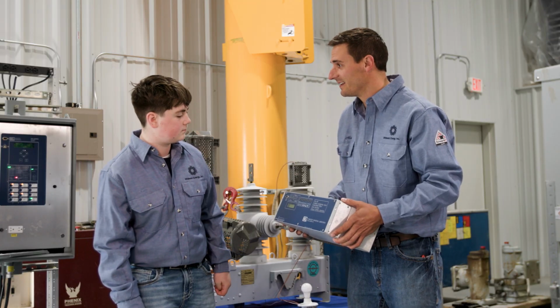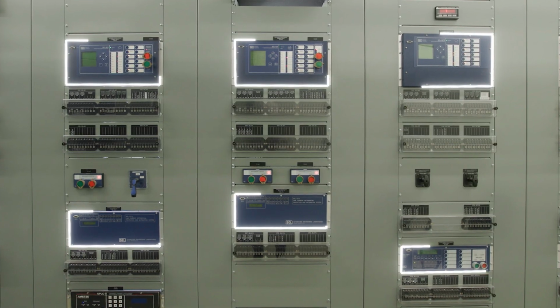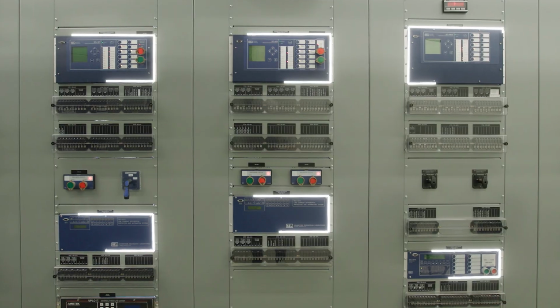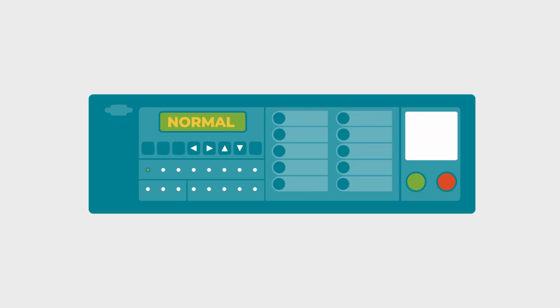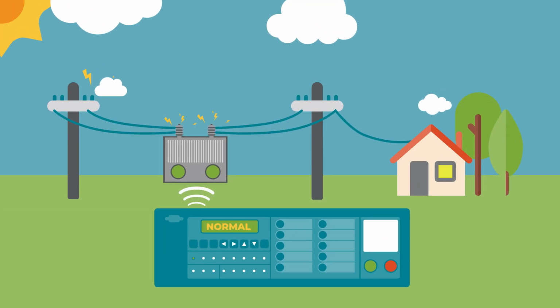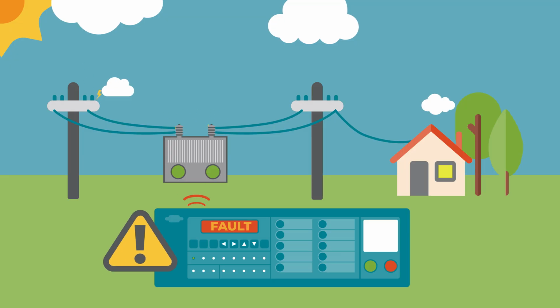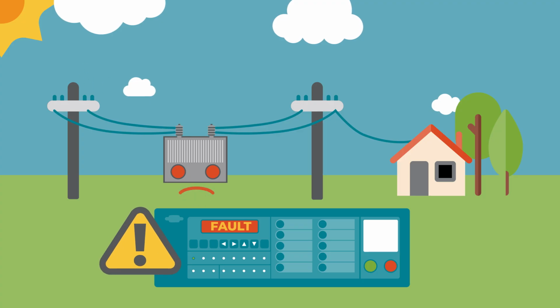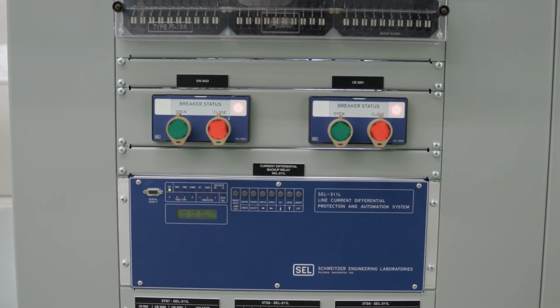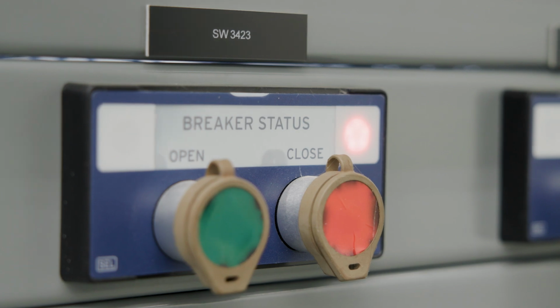This is a relay. Relays are super important inventions that help keep the electrical grid safe. These smart devices detect anything that disrupts the grid and will instantaneously tell circuit breakers to shut off the damaged sections to isolate the problem. These disruptions are called faults. This process protects the overall grid and limits the number of customers who may lose power.